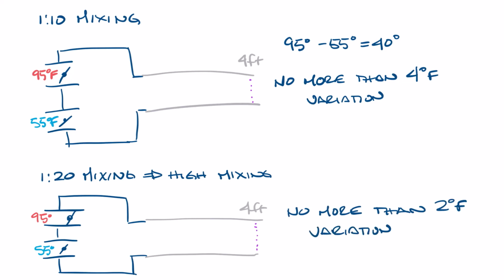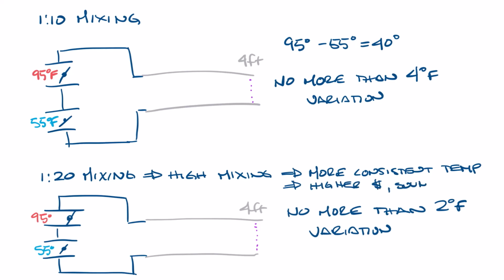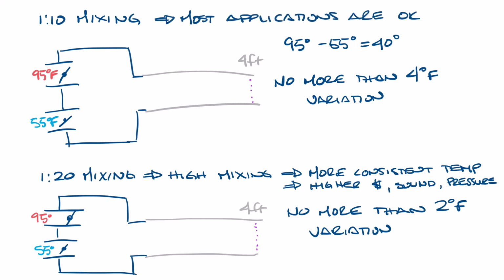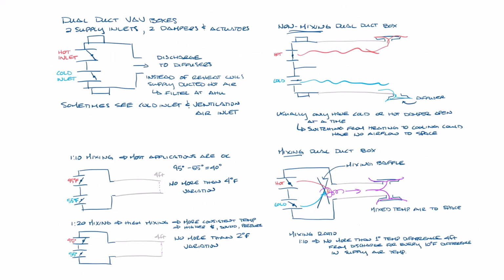The higher the mixing, the more consistent the temperature from the box. But there is a trade-off. High mixing boxes have more baffling inside to ensure the higher levels of mixing, so they cost more and they can also have higher sound and higher pressure drop. But luckily most applications are fine with 1:10 mixing. Let's bring all this back on screen. So that's how dual duct boxes work.